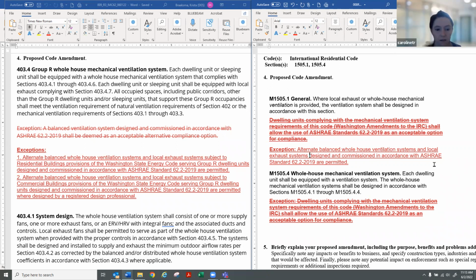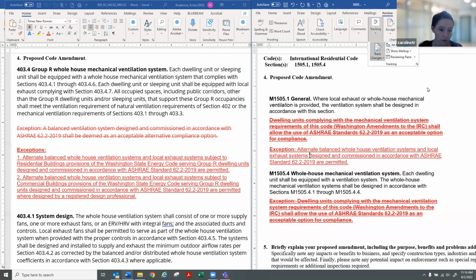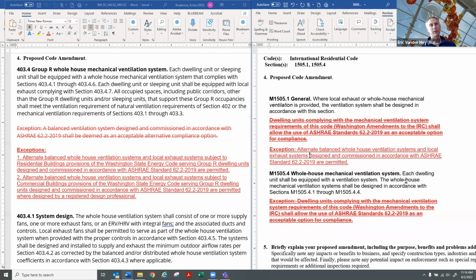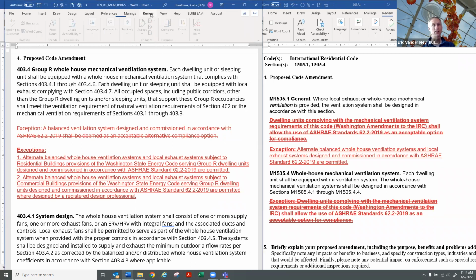Right. And then on the left, Eric, I guess I was thinking of limiting it to Group R, three stories or less. So item two, exception two, which would apply to buildings subject to the commercial energy code. Yeah, I was trying not to reference three stories or less just because of the central systems versus unit by unit. If it's a central system, then it should be designed by a registered design professional. Whereas if it was unit by unit, then it's more permissible to not be designed by a registered design professional.